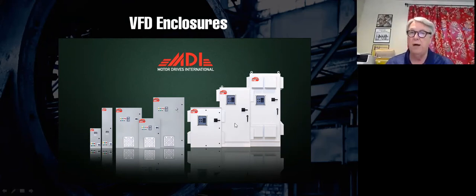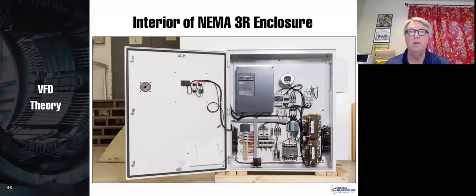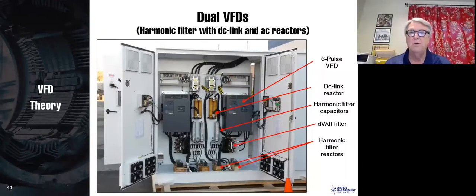The ones on the right, of course, are outdoor, and we do the same thing. We have fans and filters on our outdoor enclosures. We paint them white, and we have hoods, of course, over the filters to keep them clean and to keep rain and dirt and things from drifting into them. This is the interior of a NEMA 3R enclosure. This shows a couple of drives in a single enclosure.